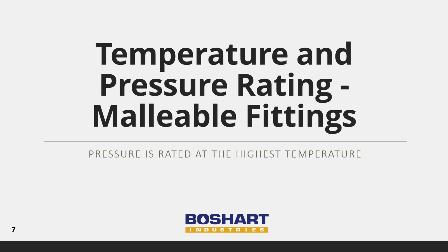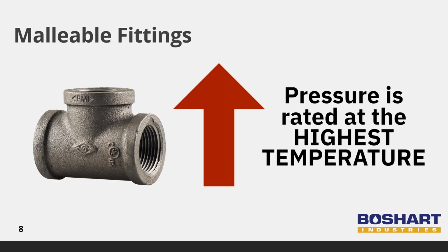Let's now take a closer look at temperature and pressure ratings for malleable fittings. The important thing to remember when working with malleable fittings is that the malleable fittings pressure is rated at the highest temperature.